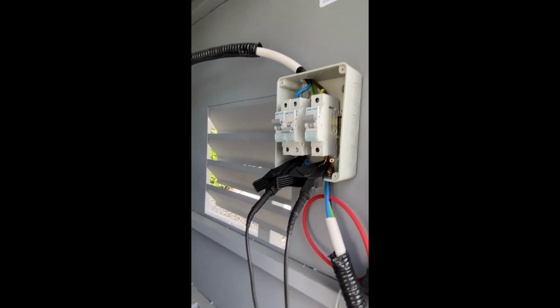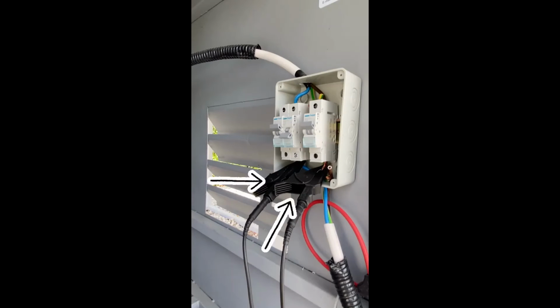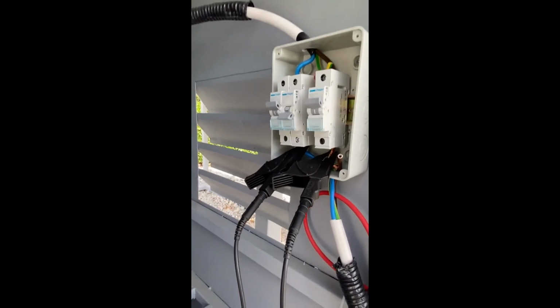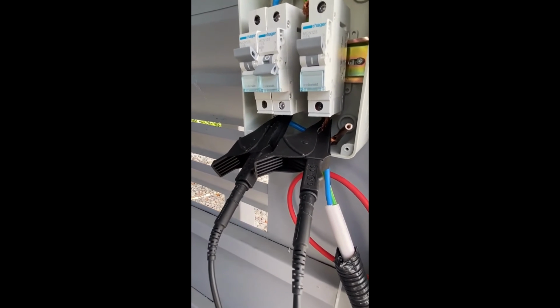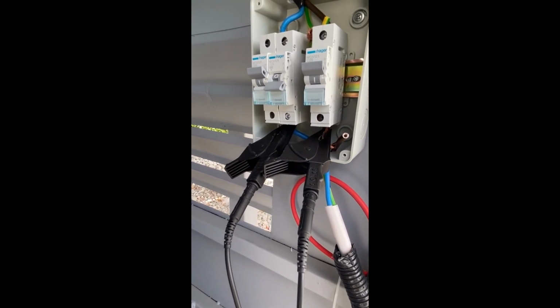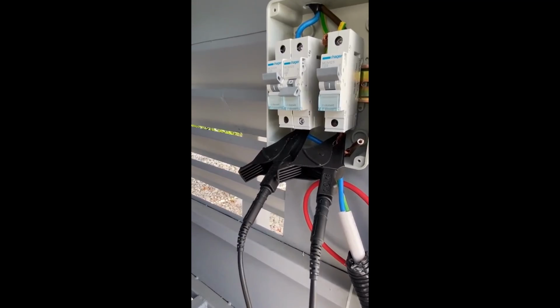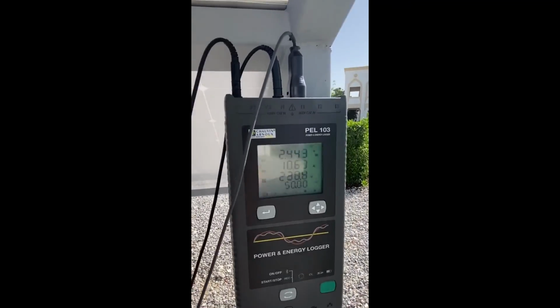Now let's go to the testing part using the PEL103 device. Two probes were directly connected to the live and neutral wires of the output cable, to measure the output voltage of our system, which is almost 230 volts right now.